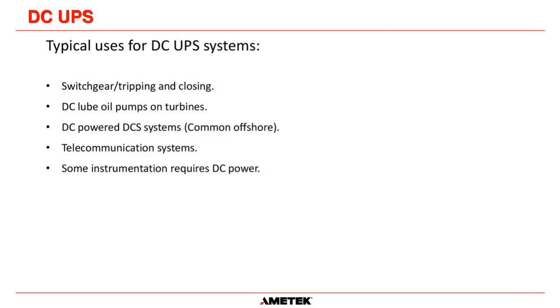DC lube pumps on turbines. That turbine shaft has to be protected at all times. The oil into the bearings on that turbine has to flow at all times. So even when there is a grid failure, that pump has to pump the oil through the bearings as the turbine spins down. So DC systems keep the batteries charged to allow the batteries to drive the DC lube pump on turbines. Very critical. If the bearings stop having oil pumped through them, they will overheat, and the shaft on that turbine will bend and warp, and that is extremely expensive.